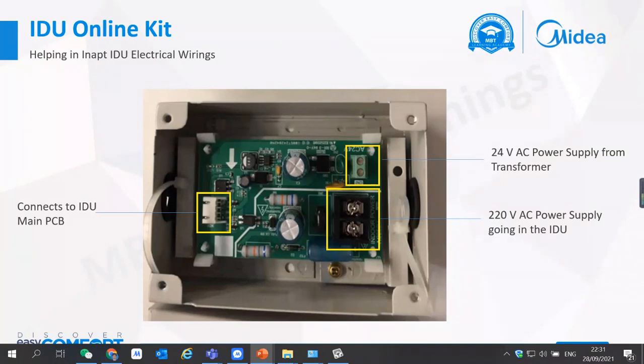For the VRF indoor unit, we suggest you have a uniform power supply. Why? Because the outdoor unit detects how many indoor units are connected to it. If the number of indoor units suddenly decreases, the system will have an error code H7 and will stop. If all power supplies are the same, and one indoor unit is damaged, then this can happen and H7 is justified. Because if the indoor unit really has a problem, its fan is not working, refrigerant is flowing inside, and liquid refrigerant can go back to the compressor, so we need to stop the system.